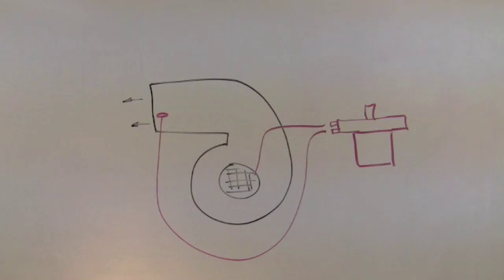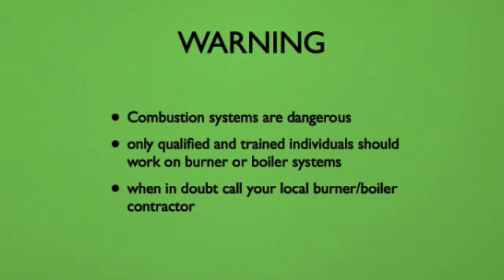Taking a look at those tubes, making sure you've got three-eighths size tubing is a good idea. Take a look to see that the fan is turning the correct direction so that you're generating pressure the way you think you're generating pressure. That should solve your problem with an airflow switch with a burner or boiler that won't operate because of airflow questions.